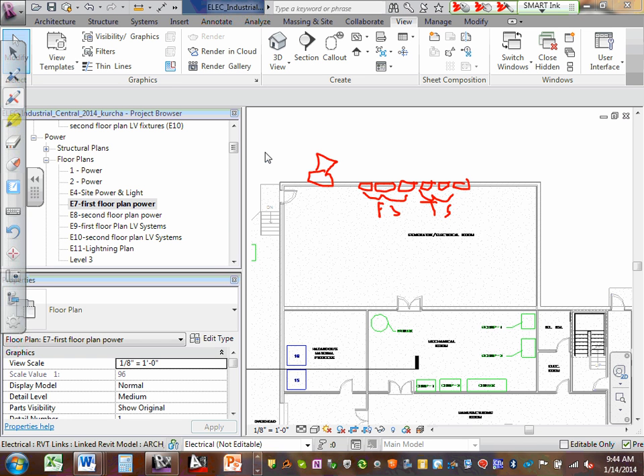Now, a tamper is not an alarm. It does not evacuate the building. What it does do is it sends a supervisory signal to the control panel. And in turn, it sends a supervisory signal to the central station, and basically it says, hey, something is off normal here, you need to go investigate it. Okay? So, there's your sprinkler system. So that's the second thing that a fire alarm system has to do, even though a fire alarm system is not required in this building. Looks like we're going to put one in, doesn't it?